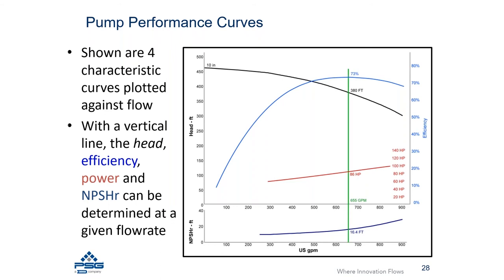In this example, the green vertical line has been added at 655 gallons per minute. Once that is set as the criteria, you follow the green line vertically until it crosses the head curve, the efficiency curve, the horsepower curve, and the NPSH required curve. Where the green line crosses the head curve, you can identify that this pump is designed to operate at 380 feet when generating 655 GPM. The pump's efficiency at this point is 73%, which is very close to the best efficiency point.